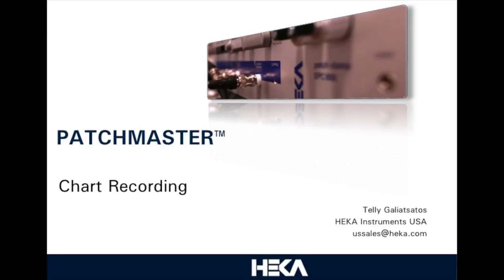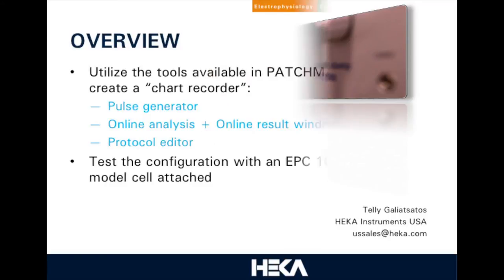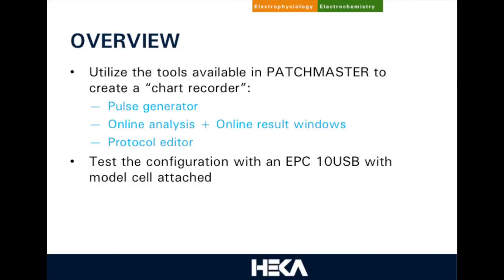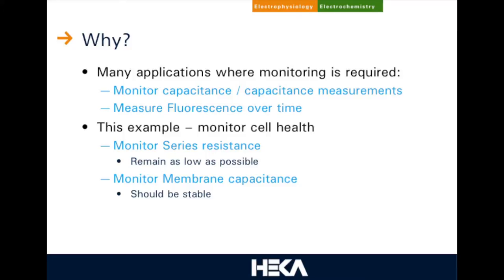Thank you, Jan. The goal of my presentation today is to go step-by-step through the various settings required in the pulse generator, the online analysis, and the protocol editor, which will lead to a Patchmaster configuration that provides both a high-resolution acquisition and a low-resolution chart recorder. I will be using the EPC-10 USB to test the configuration with a model cell attached. Chart recording is needed for applications where monitoring is required — we can monitor capacitance, fluorescence over time. In this example, we're monitoring series resistance, which we want to remain as low as possible, and membrane capacitance, which we want to remain stable.